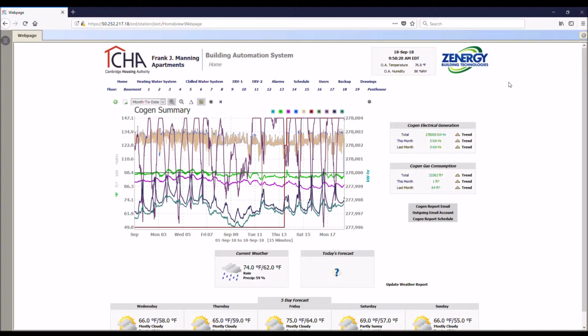Downstairs there's also a row of routers - they are MSTP to BACnet/IP routers. All the controllers in the building are wired to a 2-wire MSTP bus, and those are all wired back to those routers in the basement. There are roughly 10 of them, maybe 12 total. All of those lights need to be flashing at all times for the communication to stay up. Those little routers are roughly the size of an iPhone, round and a little thicker - twice the thickness. All those need to be powered and operating.